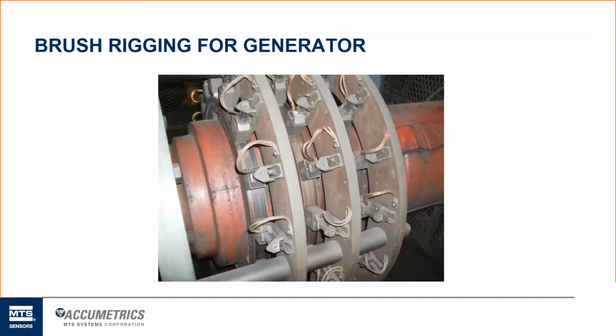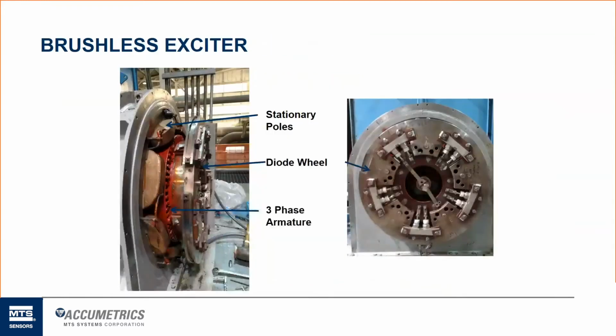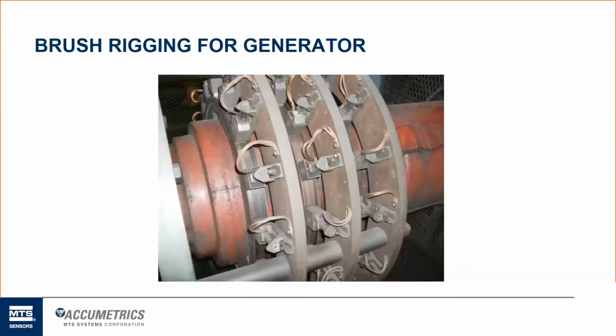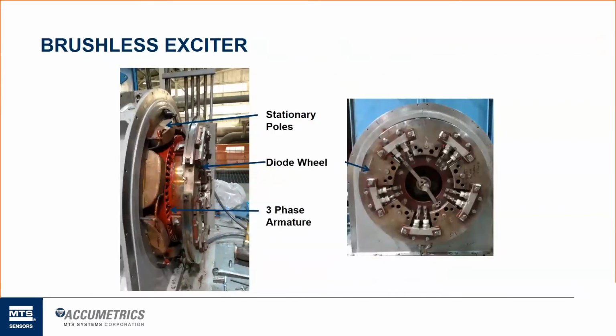In contrast to the brushed systems, they have what's called a brushless exciter. You can think of a brushless exciter basically as an inside-out motor, or an inside-out generator, sorry. So they have the three-phase AC windings, and all of the armature and electronic circuitry and everything that is required to produce the DC field out on the rotor itself. So you basically get three-phase AC currents on the rotor. They have to be rectified using silicon diode rectifiers to produce that DC current source that then powers the generator itself.